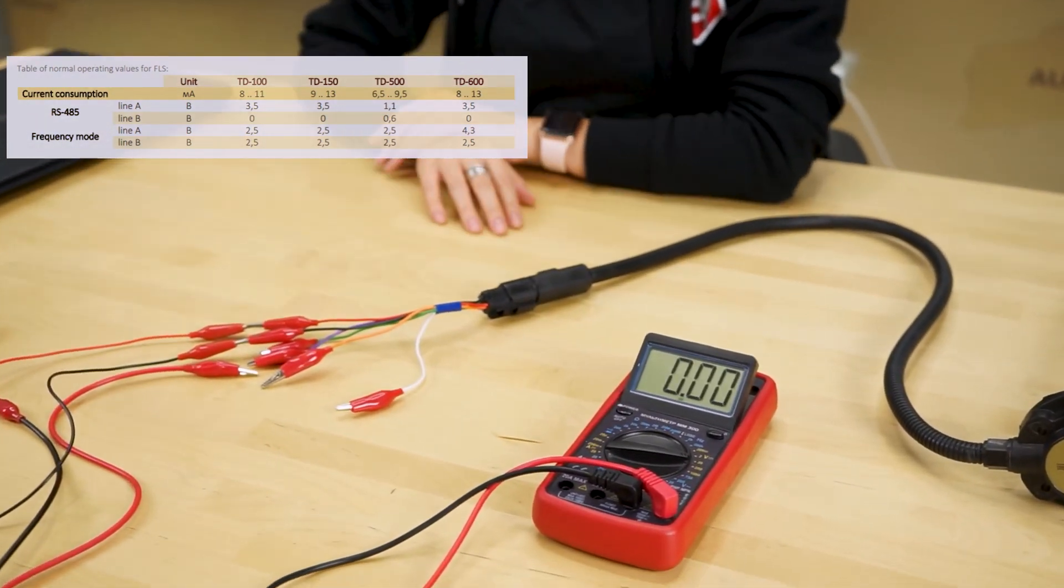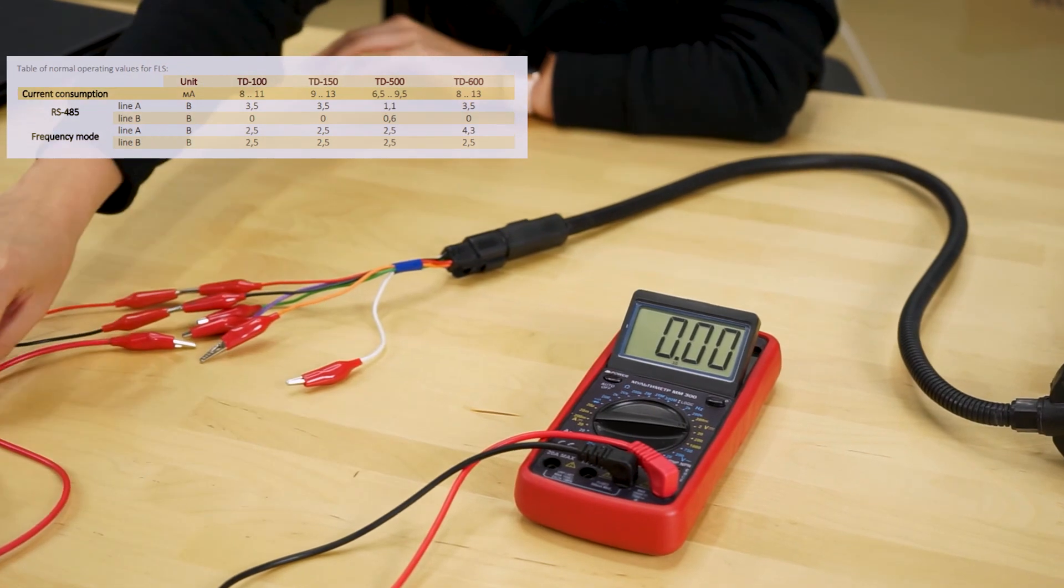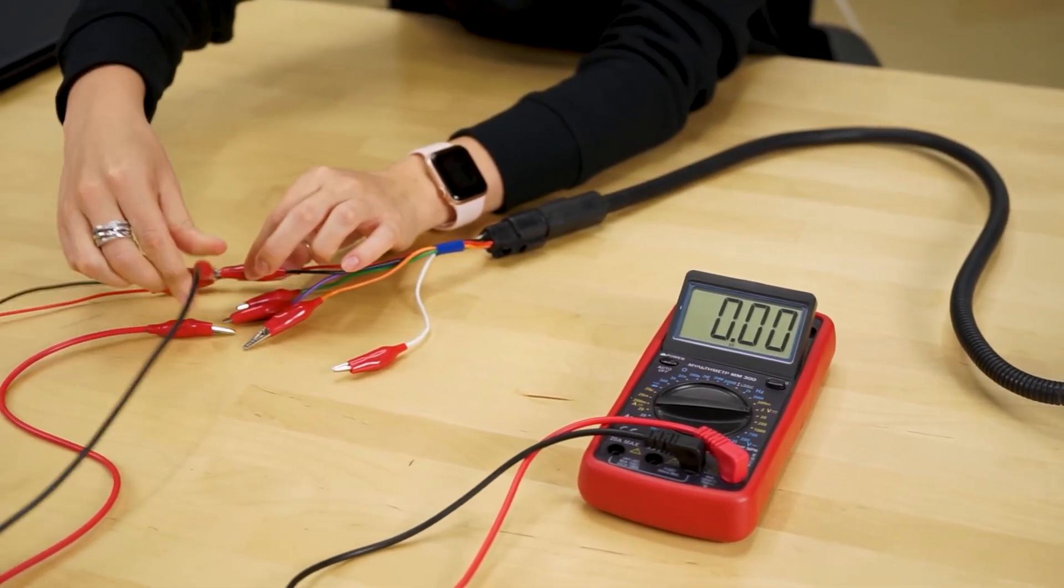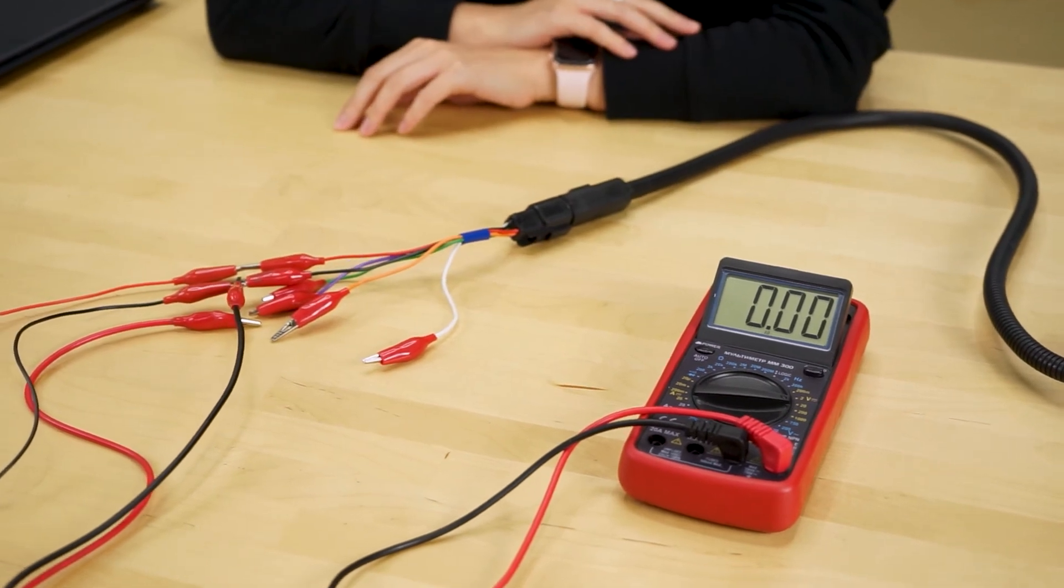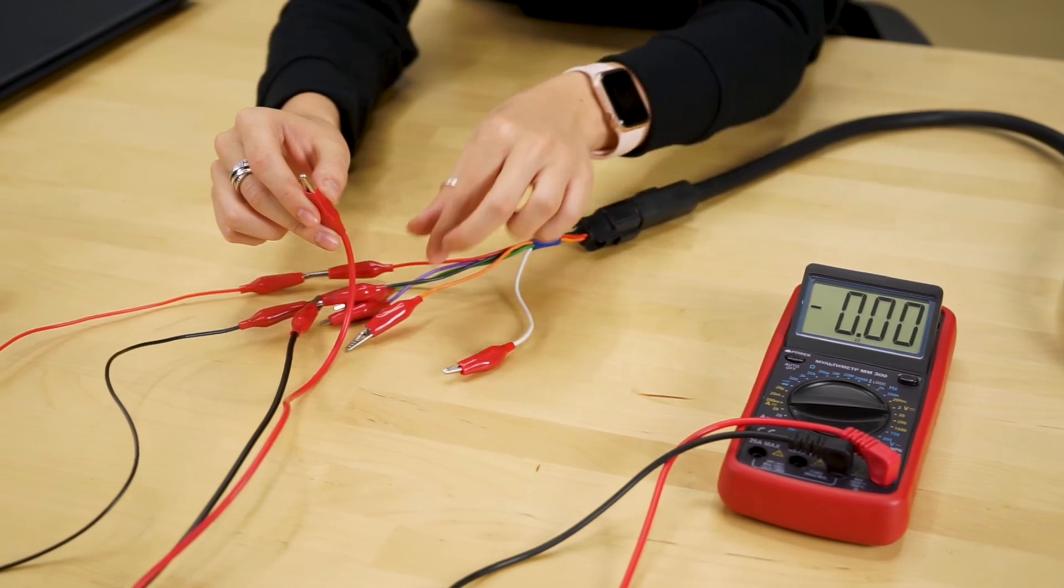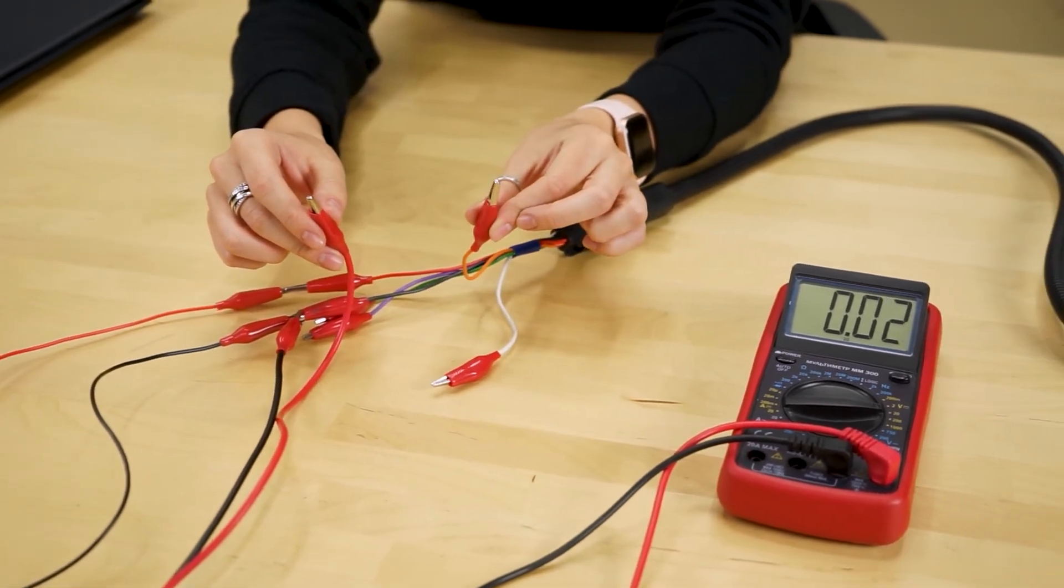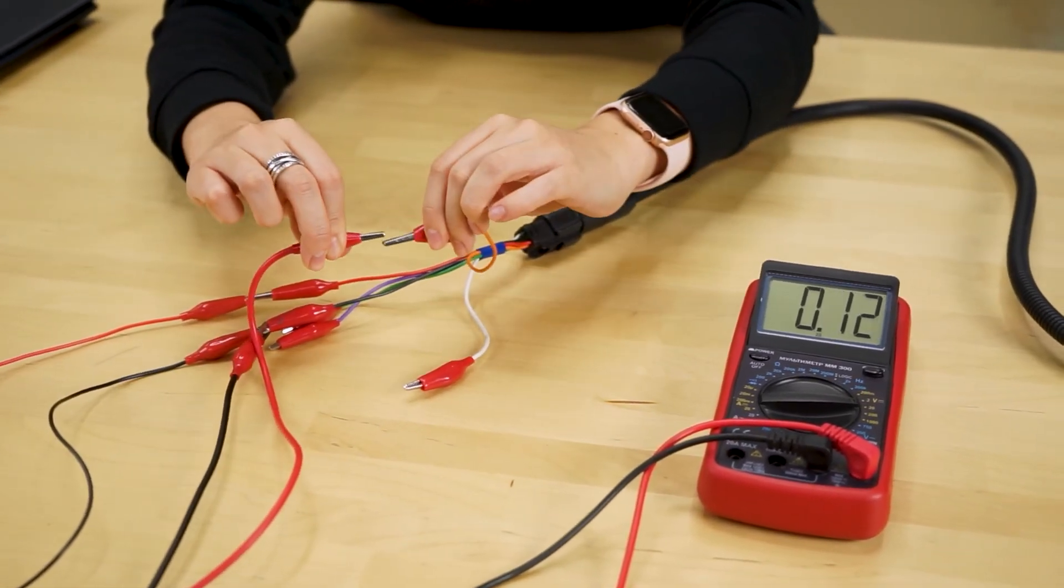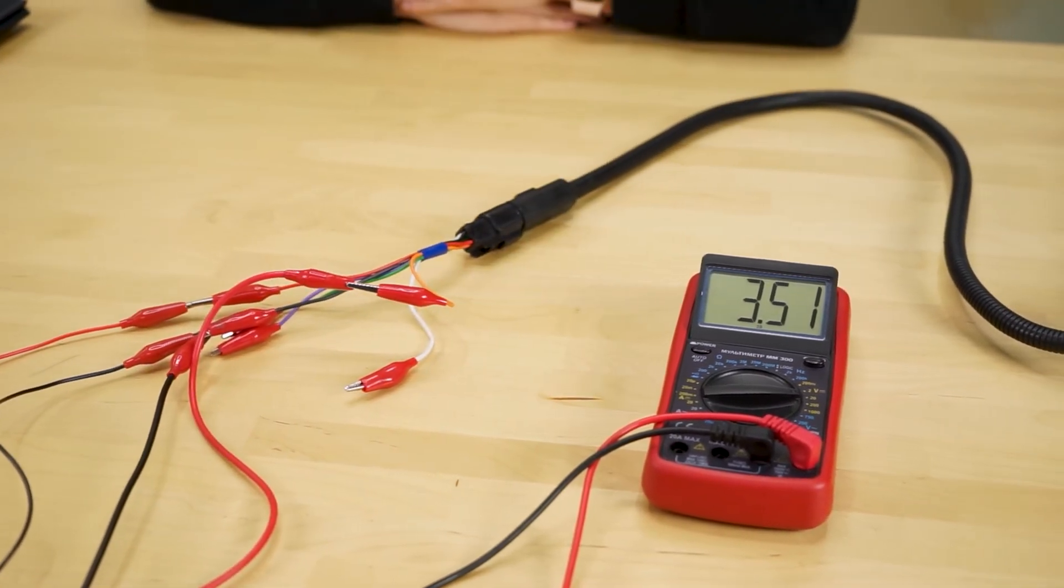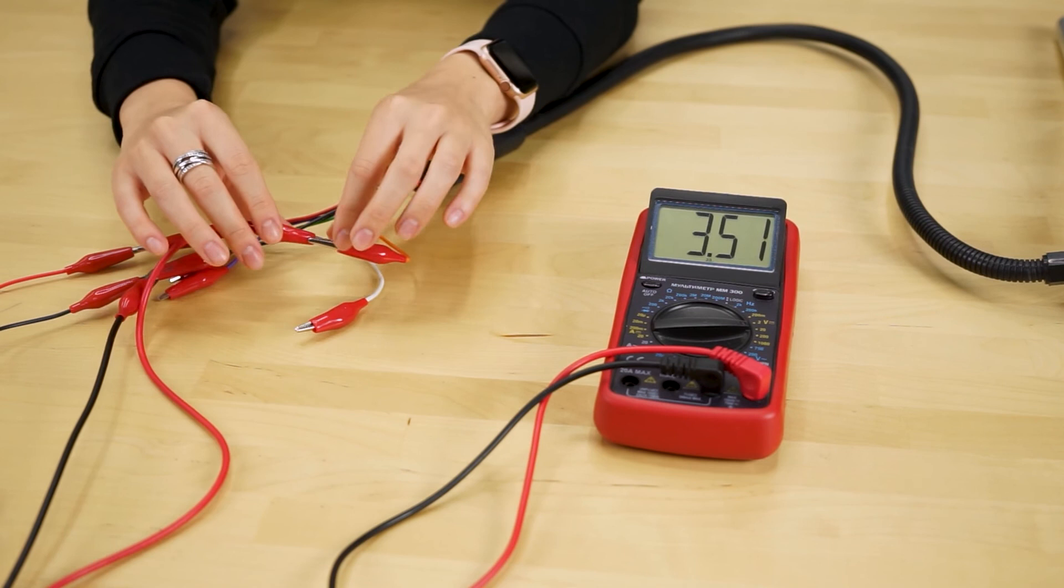To do so, connect one of the multimeter's cables to the negative of the sensor and the other one to the output that needs to be checked, for example the line A of the RS485 interface, the orange cable. The voltage there must be around 3.5 volts if the sensor is working in the RS485 mode. On the white wire there should be zero volts.